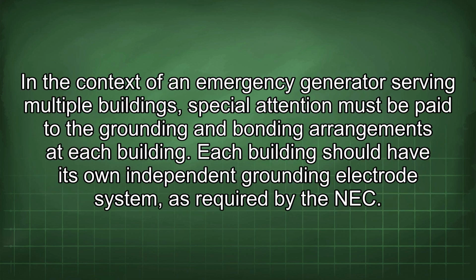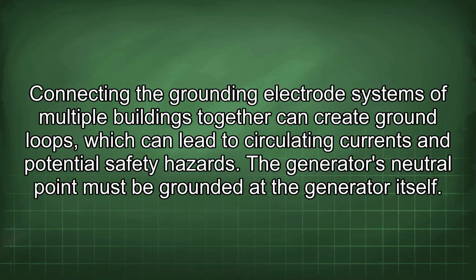In the context of an emergency generator serving multiple buildings, special attention must be paid to the grounding and bonding arrangements at each building. Each building should have its own independent grounding electrode system, as required by the NEC. Connecting the grounding electrode systems of multiple buildings together can create ground loops, which can lead to circulating currents and potential safety hazards. The generator's neutral point must be grounded at the generator itself.